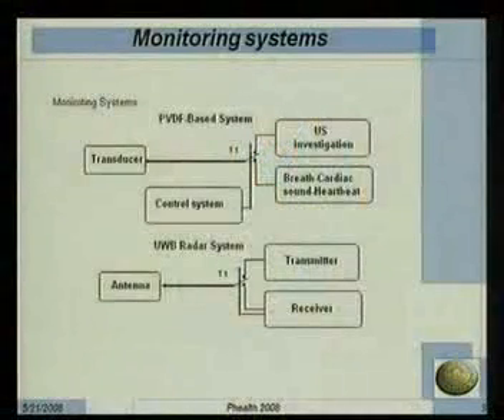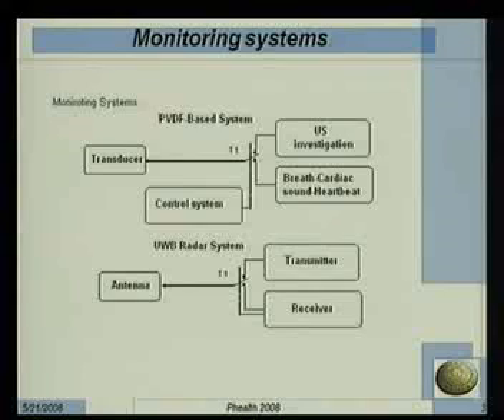Here I will describe two different monitoring systems. The first one is based on ultrasound technology, and the second on radio frequency technology. The first system is characterized by a special transducer which has the specific property of having a low Q factor, which implies a wide bandwidth, and this allows us to use this transducer at low and high frequency. So we can drive the transducer to work as a simple microphone, a simple piezoelectric transducer, in order to detect the sounds coming from the heart and breathing signals and heartbeat.